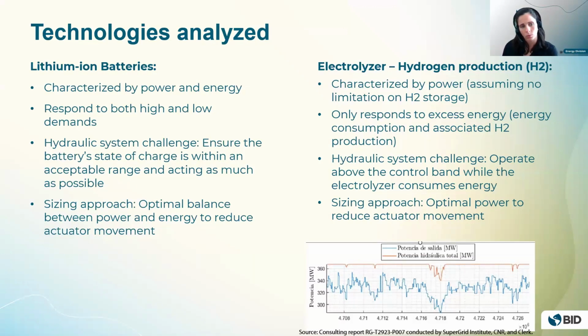Then the other technology was electrolyzers for hydrogen generation, which are characterized by their power. This technology can only respond by consuming energy. The hydraulic system must operate above the control band to allow the electrolyzer to consume the necessary energy for frequency regulation. The operating point of the electrolyzer should be shifted to the middle of its operating range. Just as an example, if it's from 10 to 100%, it should be set at 55% of its nominal power.